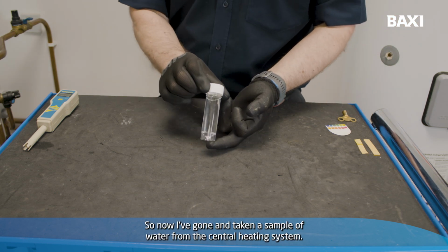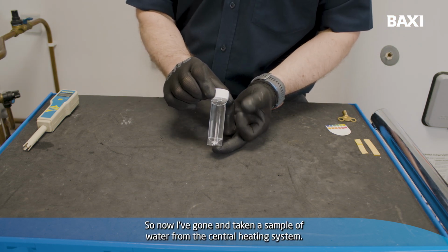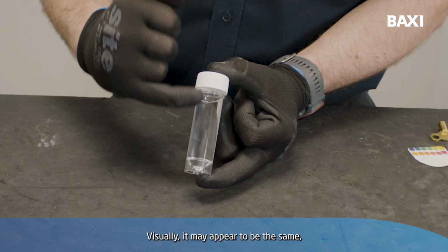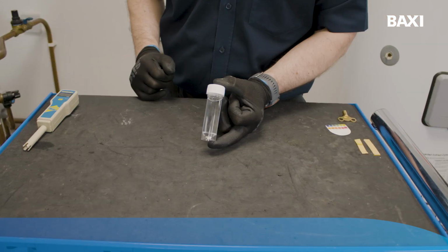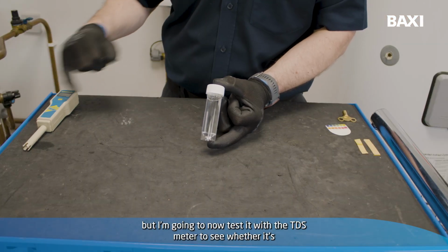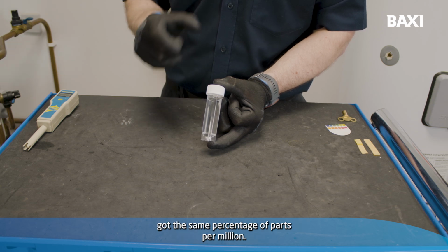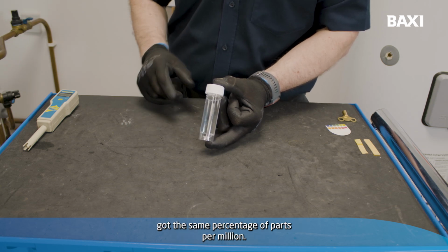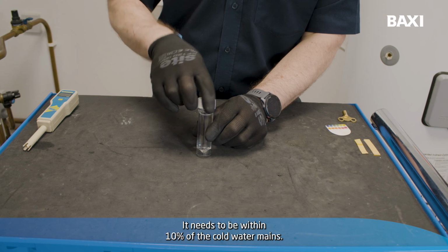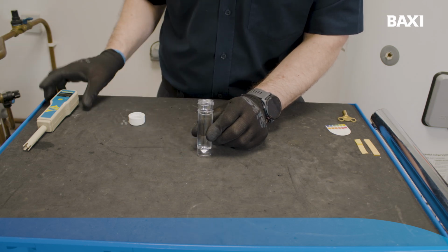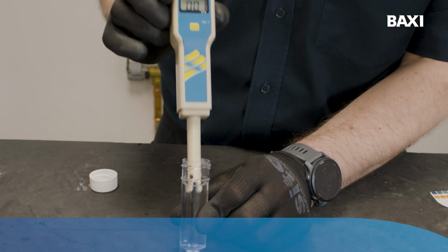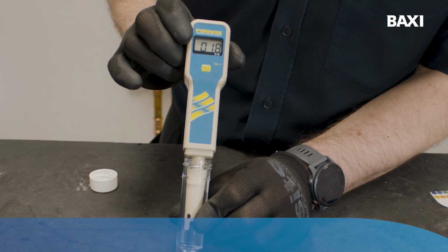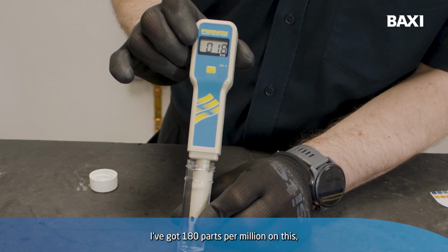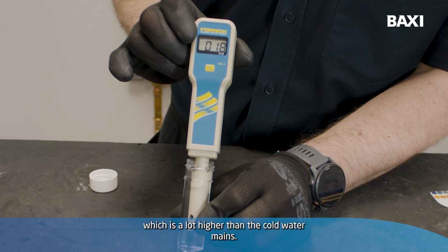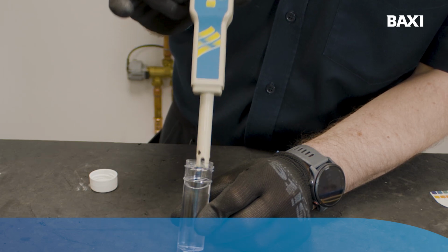So now I've gone and taken a sample of water from the central heating system. Visually, it may appear to be the same, but I'm going to now test it with the TDS meter to see whether it's got the same percentage of parts per million. It needs to be within 10% of the cold water mains. Now, as you can see from the screen there, I've got 180 parts per million on this, which is a lot higher than the cold water mains.